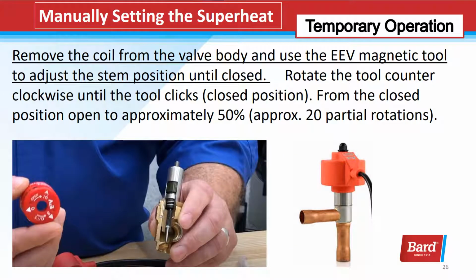We just went through and checked out all the components. However, if we found a defective part during the process and have to order that part, the valve will have to be set up manually in order to get this unit back into service. Remove the coil from the valve body and use the EEV tool to adjust the stem position until closed. Rotate the tool counterclockwise until the tool clicks. From the closed position, open to approximately 50%. That is approximately 20 partial rotations in the opposite direction.